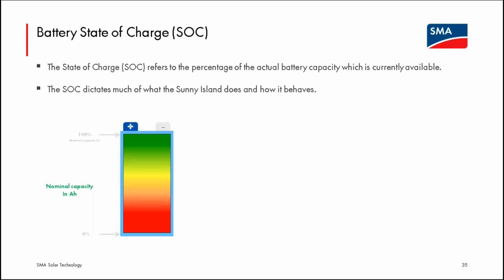Sunny Island microgrid operation is generally driven completely by the state of charge of the battery bank. The master will monitor the state of charge of its cluster's battery bank and will really dictate what happens with the cluster. If the state of charge gets too low, the Sunny Island will shut down the whole microgrid to protect the health of its battery bank. So its primary goal is to maintain the health of its battery bank, not actually operate a microgrid.